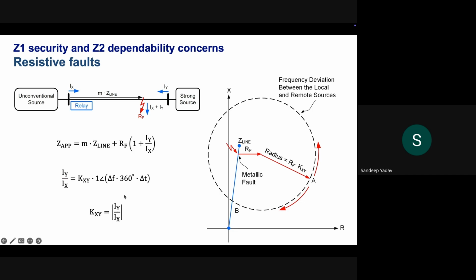So if you take a look at the locus of this impedance, this is the relay location. It goes from this point up until the fault point, which is M into Z line, and then because this is the RX plane, the fault resistance RF will be parallel to the R axis, the resistive axis. So this is RF. Now, depending upon the expression IY by IX, this point could be anywhere on this trajectory.